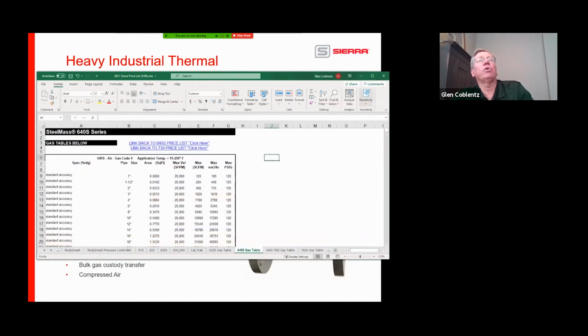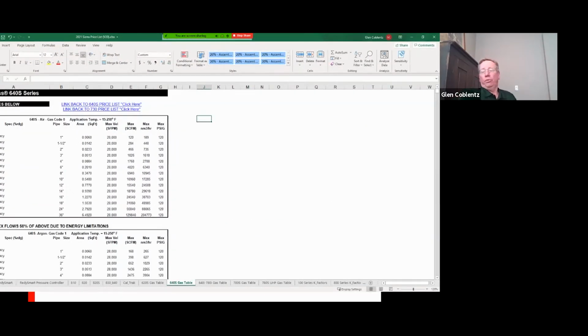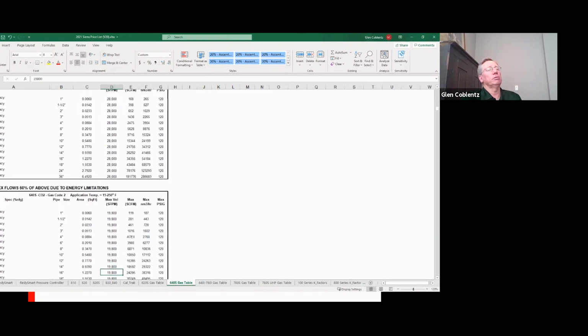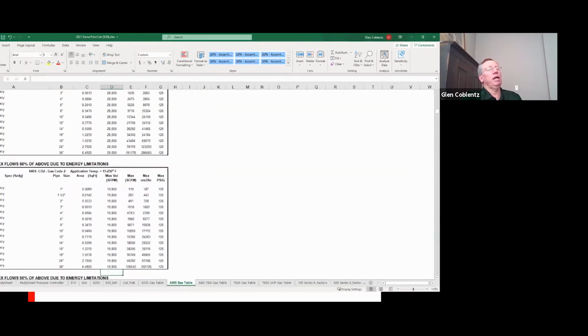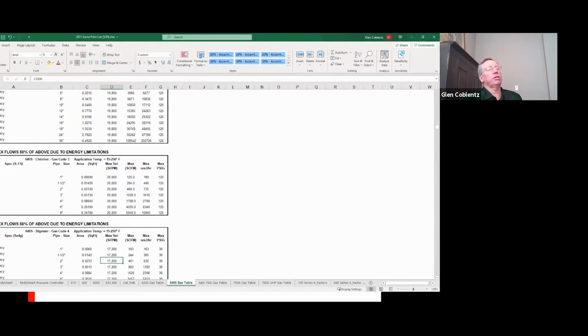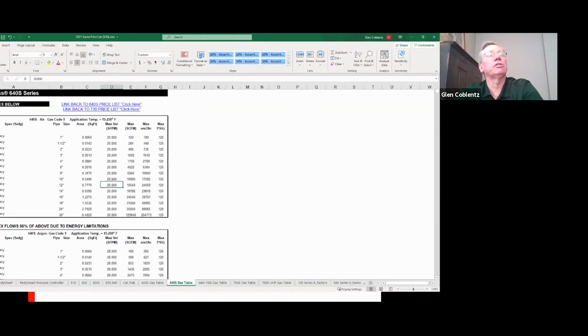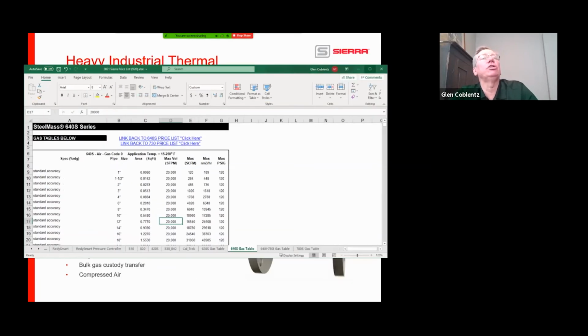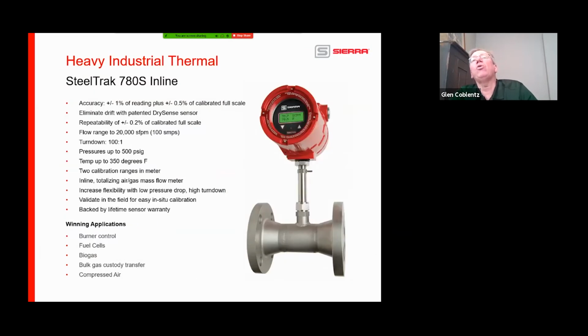So let's look at the 640S table and the gas table. That's why these are in the price book. This is air, maximum is 20,000. This is argon, 28,000. CO2, 19.8. Digester gas, 17.2. So the whole point of this is, depending on what gas you're using, the full scale flow rate will be different for our legacy products. So you need to keep that in mind when you're sizing those up. And we'll cover this a little bit more in detail a little bit later.